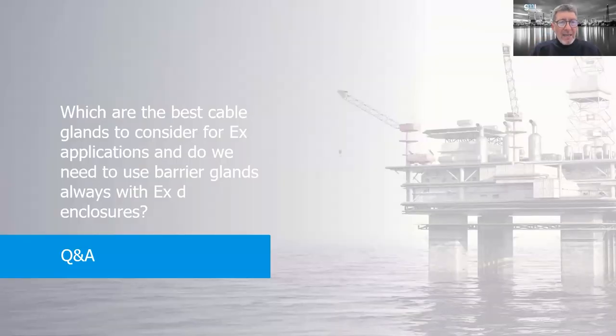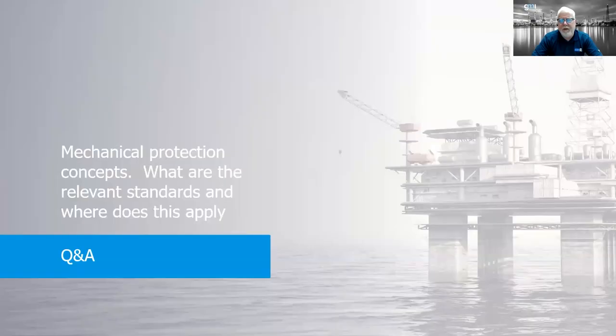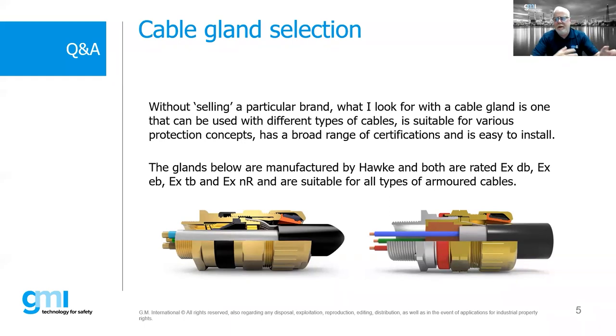Question: which are the best cable glands for EX applications? Do we need to use a barrier gland always with an Ex d enclosure? There are universal-type glands — one brand is Hawke — where one gland is certified as EXD, EXE, dust, and restricted breathing simultaneously. Both glands shown have basically the same certification. The one on the right is a flame proof gland; the one on the left also has flame proof capability. You could use the gland on the left for direct entry into flame proof — but that's a whole other webinar. The positive thing is that those universal glands can be used in almost every protection concept, so you don't have to worry about stocking different gland types, though they are probably a little more expensive.